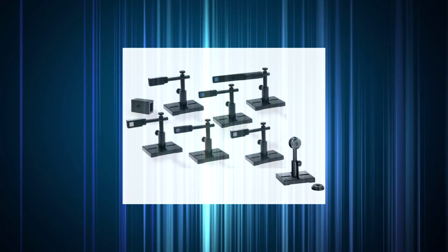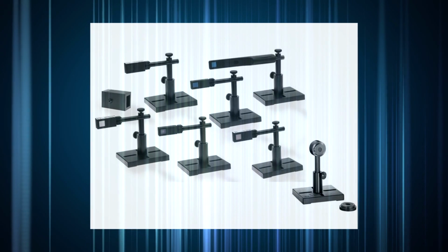How is laser power or energy measurement affected by incidence angle? The short answer is it depends on the type of sensor, or more specifically on the type of absorber that's being used. In this video, we'll look at each sensor type and we'll understand to what degree incidence angle matters when you're trying to measure laser power or energy. Let's begin with photodiode sensors.